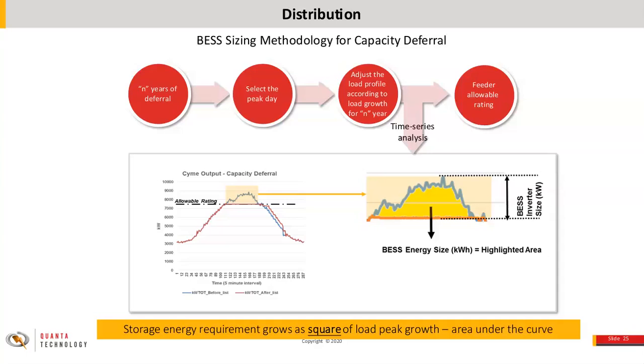But the size of the battery is the area under the curve. And as we move the curve up, the area increases quadratically with time. So when we look at cost effectiveness for deferral, we're in a kind of race. The longer you can defer the station expansion, the longer you've got savings and the better the net present value of those savings. But the longer you do the deferral, the bigger the battery has to get and the costs go up. But over time, the battery costs per megawatt hour may come down. So there's an interesting but complex race, time-wise, in doing this analysis.